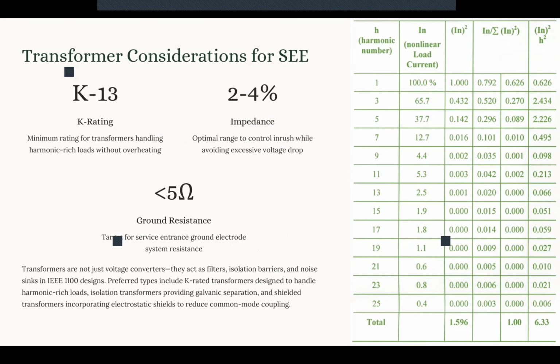Now, we mentioned briefly that the transformer in our power system distribution plays a critical role when we talk about the power quality that is delivered to our sensitive equipment. It's not just about the voltage conversion, like a step up or a step down. Okay, these transformers also serve as filters and isolation barriers and even noise sinks. Okay, so IEEE 1100 requires some selection criteria when you want to select the transformers that you want to install in your system.